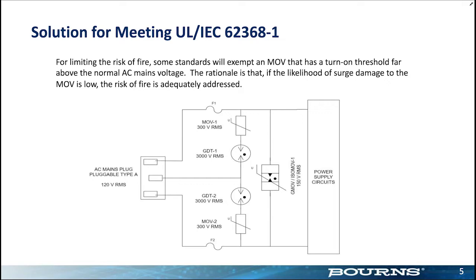What's going on there is the GDT is a gap. It's a gas discharge tube. It's like a little neon bulb. Voltage gets high enough, it'll trigger and become conductive. But until that time, it's an open circuit. It's a gap. There is no leakage. So that solves the leakage aging problem for MOVs.